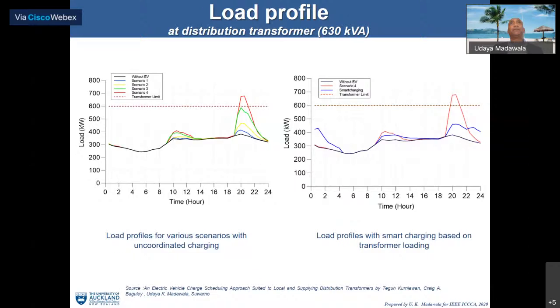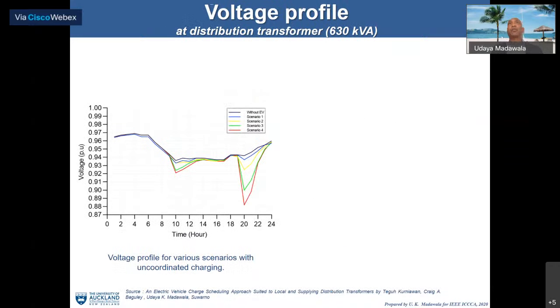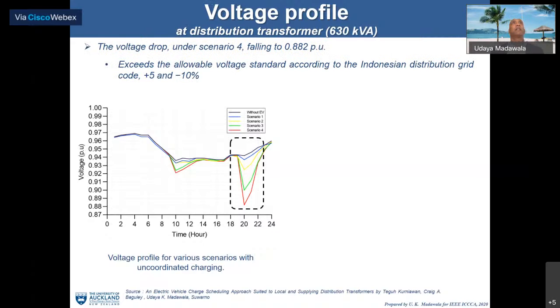Looking at the same transformer, consider the voltage problem rather than the transformer loading—what actually happens if it's the end of the line, a weak line? Can we cater for the customers or consumers connected to that line? You can see the voltage drop under scenario 4 is 0.882, which exceeds the allowable limit in Indonesia. So what can we do? How can we mitigate the problem?